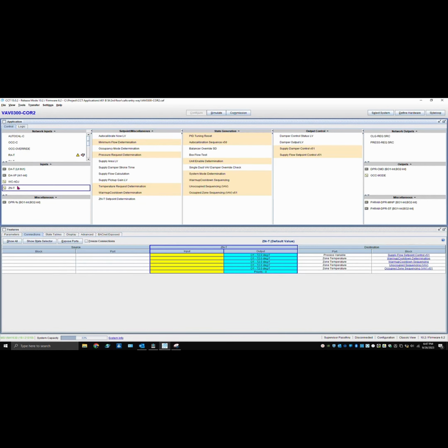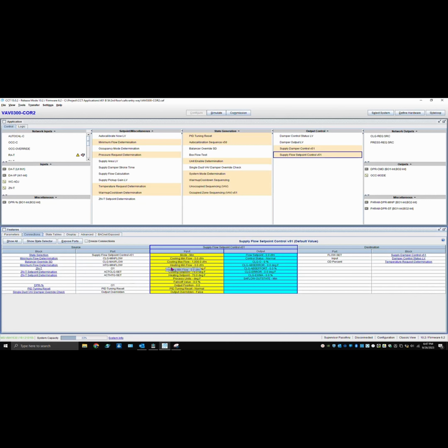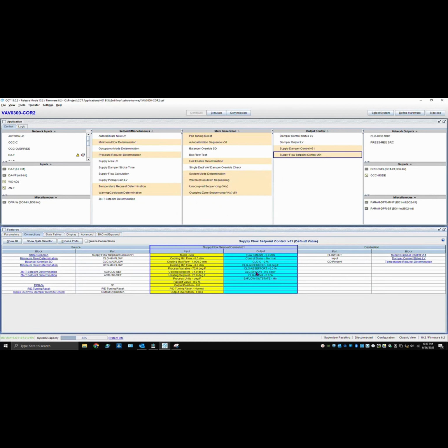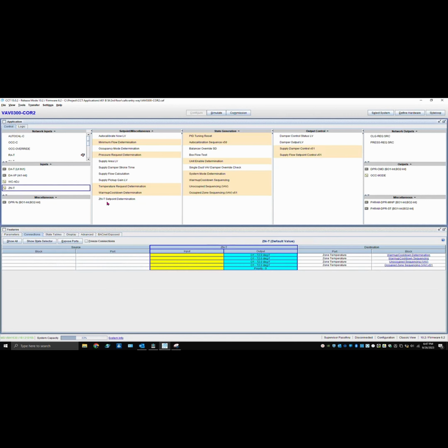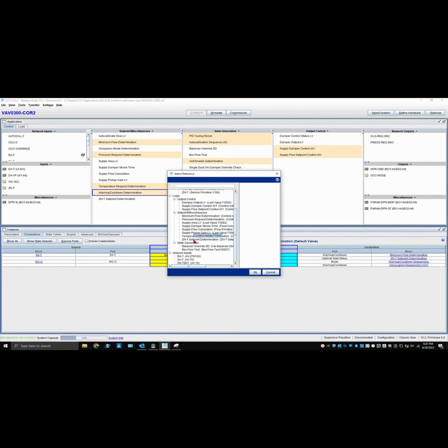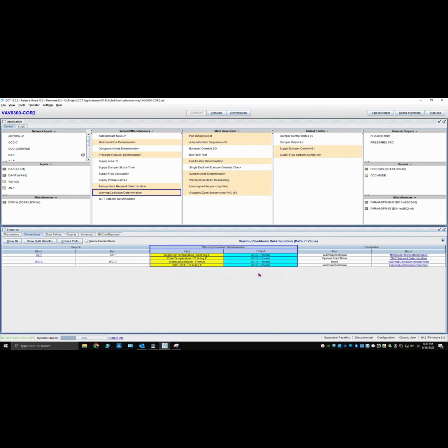And now we're going to do the exact same thing we did with the master controller. We're going to basically break the connections that are looking at zone temperature and redirect them to this RA-T network input. When you do break each of these connections, you'll find that the connection is actually at the bottom of the list because it's a network input, as you can see here.